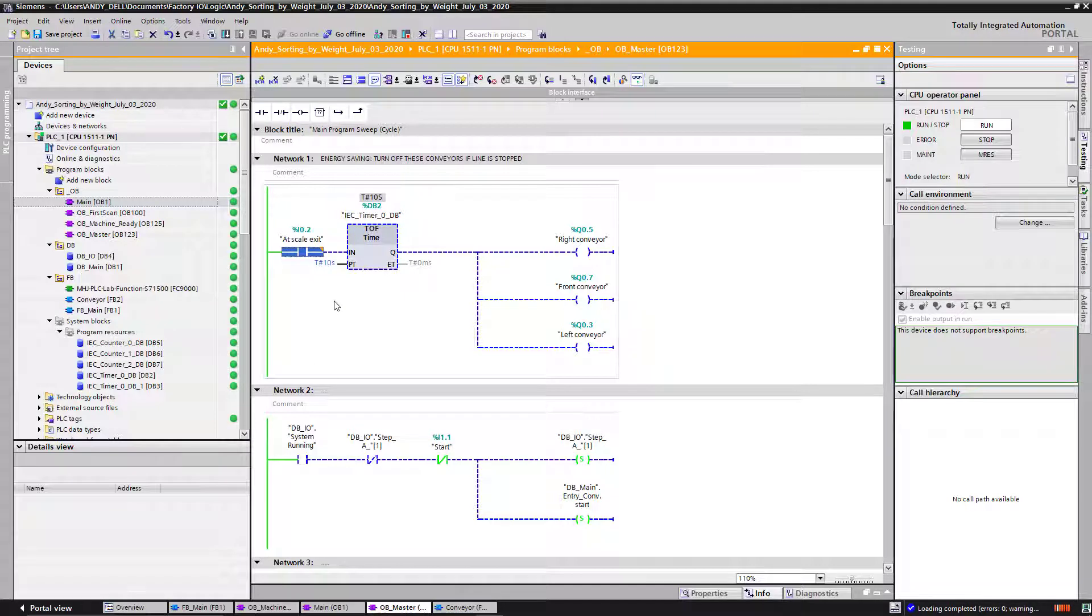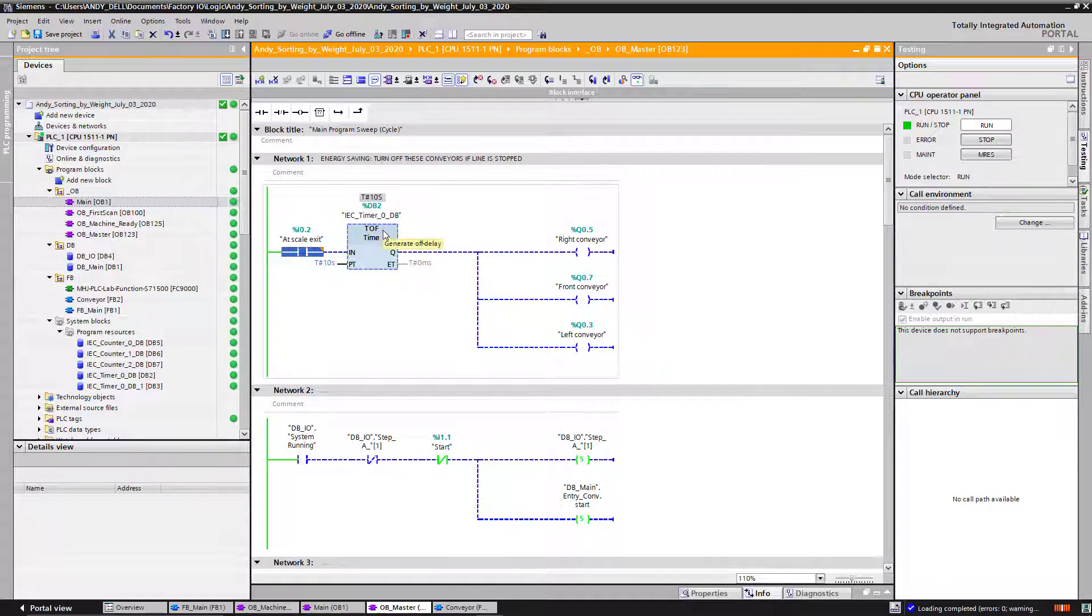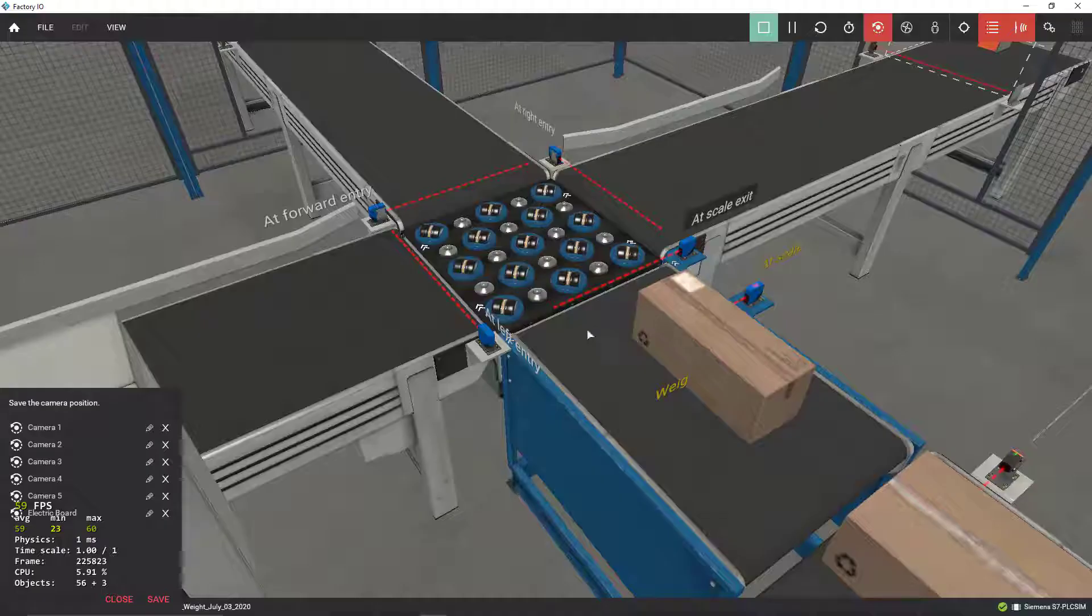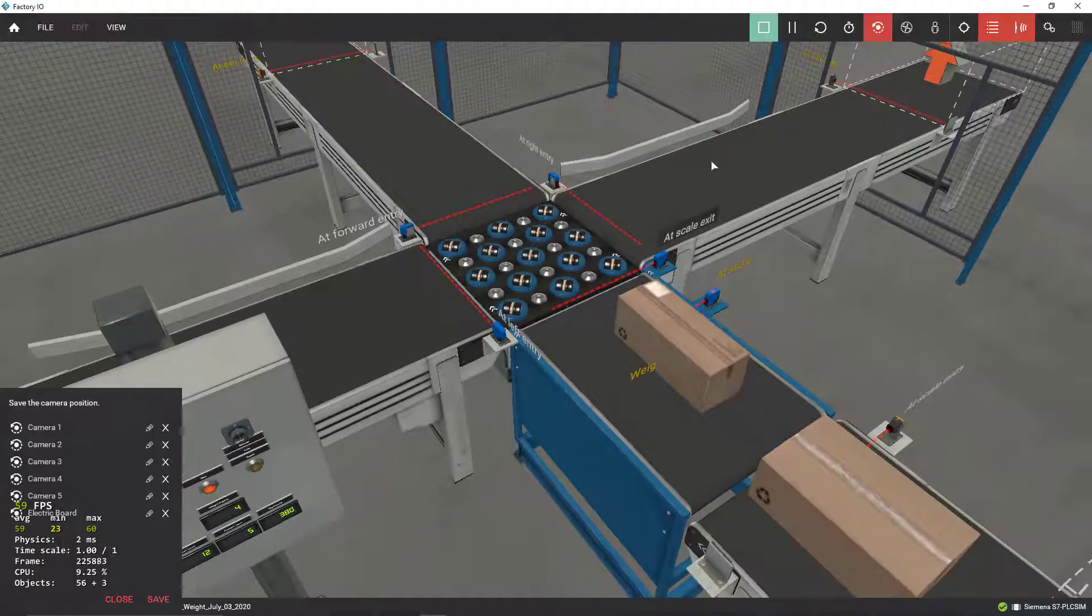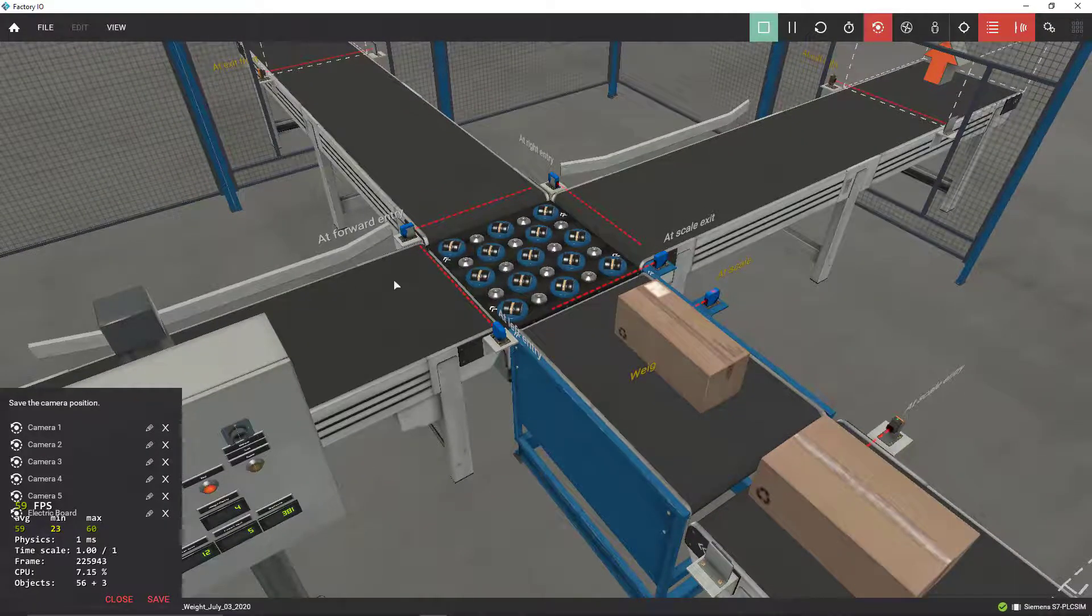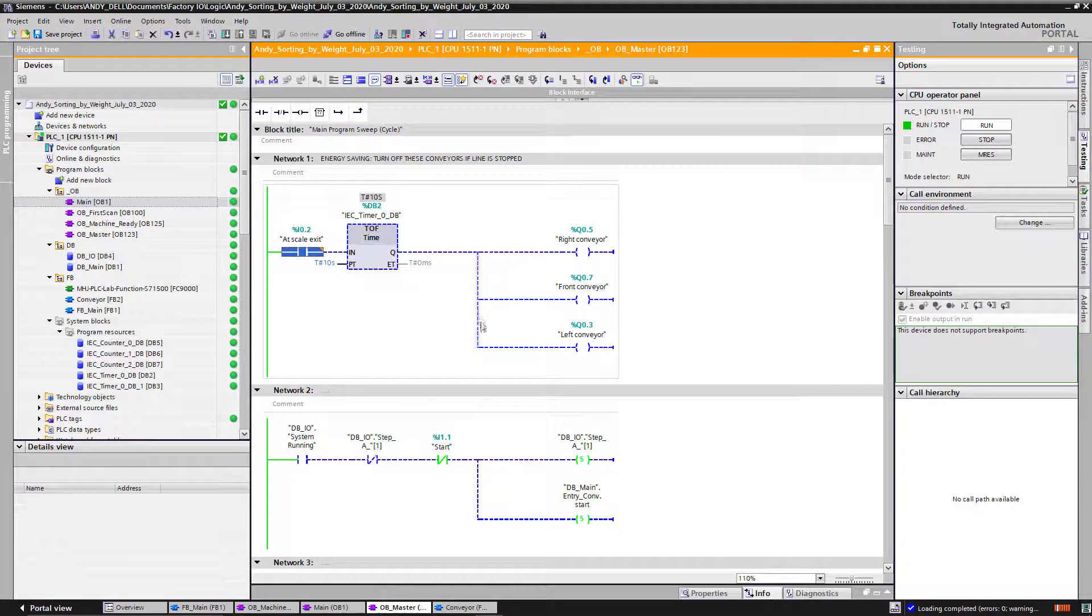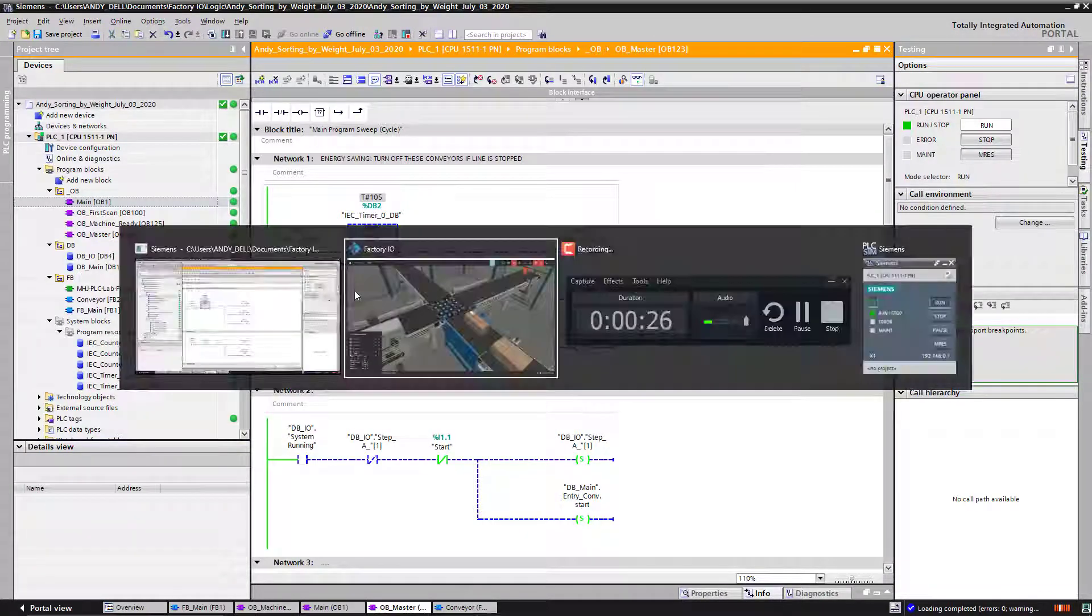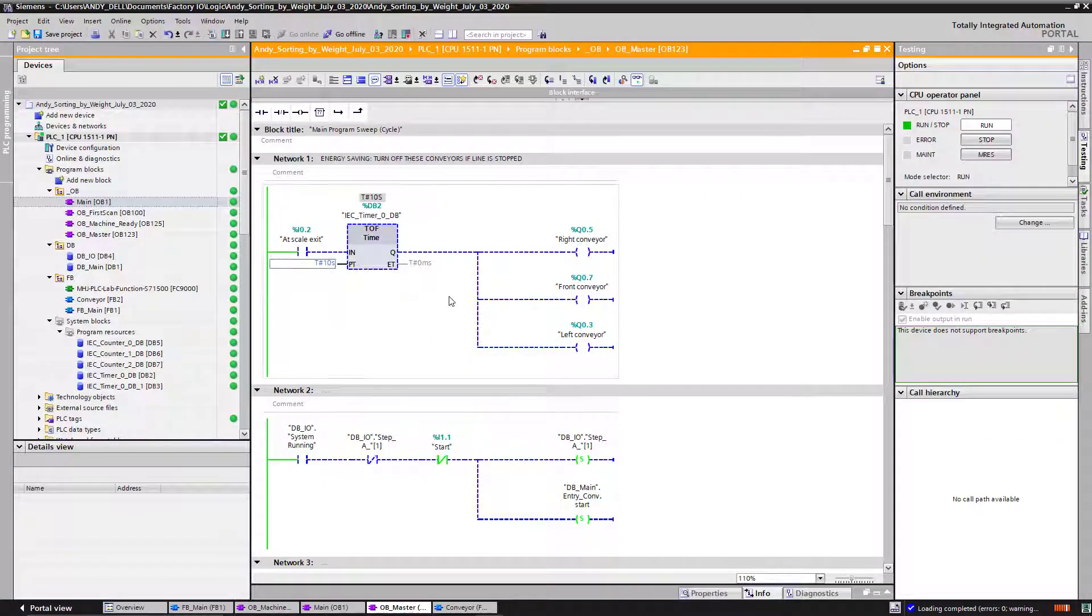If this tag over here is not seeing an off-to-on transition, then I'm going to use a timer, off conveyor count timer, and then I'm going to run these three conveyors, which are my exit conveyor one, two, and three. I'm going to run them for only 10 seconds. That will save energy to the plant.